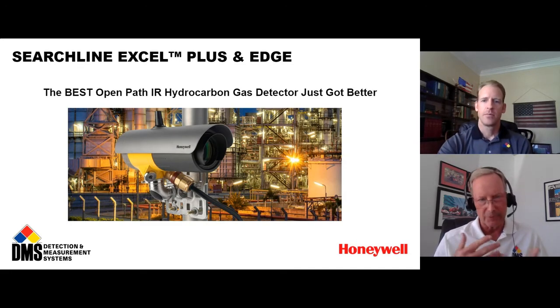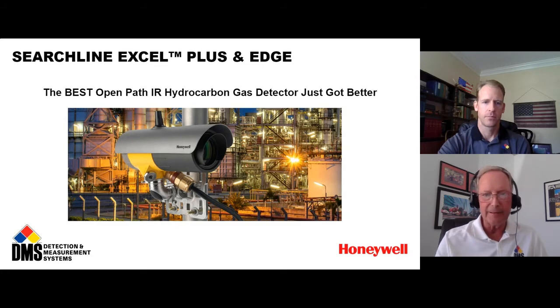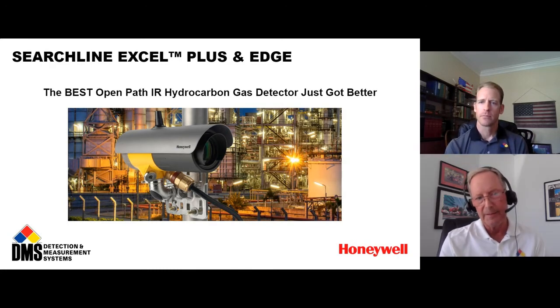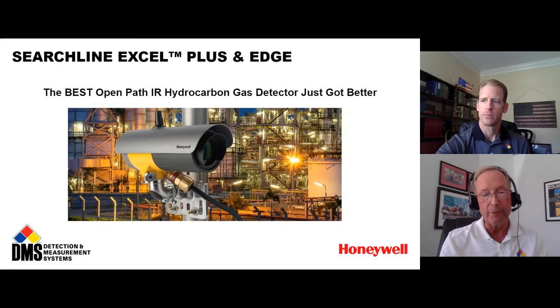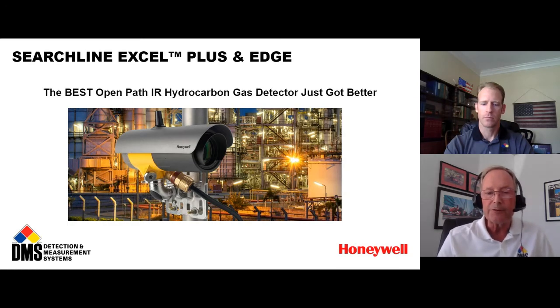And I want to start again. We're going to be talking about the Searchline Excel Plus and Edge, the new Open-Path infrared hydrocarbon gas detector. And in the event that there's anybody in the crowd who isn't familiar with what open-path hydrocarbon gas detection is, basically an open-path hydrocarbon gas detector is a detection system where we have an infrared light source that projects an infrared beam across an extended distance of hundreds of feet to an infrared receiver that's located on the other end. And most any hydrocarbon gas that crosses the beam at any point between the source and the receiver is not only going to be detected, but the detector will also measure the volume, not the concentration, but the volume of hydrocarbon gas that's present within the beam at that period of time.